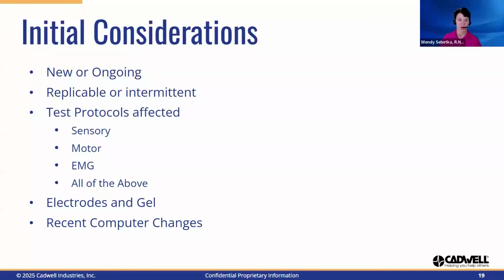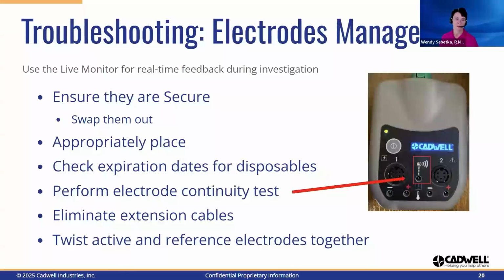In today's day and age, we also need to take into consideration recent computer changes such as Microsoft and software upgrades or hardware replacement. While the potential may be low, being aware of these changes may play a key role in helping us resolve these issues. The first thing to consider is making certain proper electrode management techniques are being followed. The easiest step to take when trying to eliminate noise is to replace the electrodes. Replacing the electrodes will resolve most new consistent noise issues.